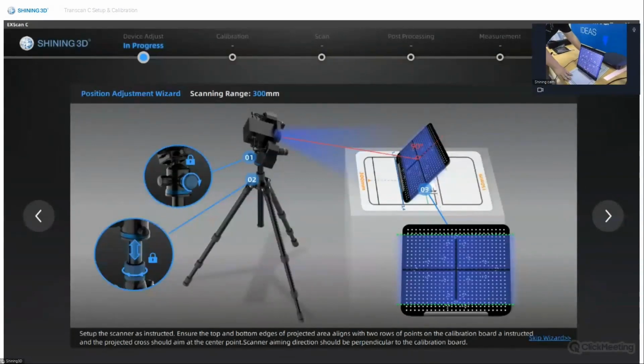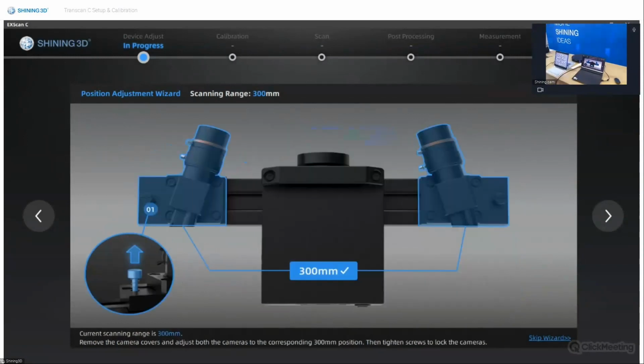All right, so this is how you set up the device and the calibration board. This is actually the most important step of the whole calibration, the whole scanner setup. If the scanner angle is not right or the distance is not right, the calibration will 100% not be able to pass. Okay, so after it's set up, the next step is adjusting the scanner range.